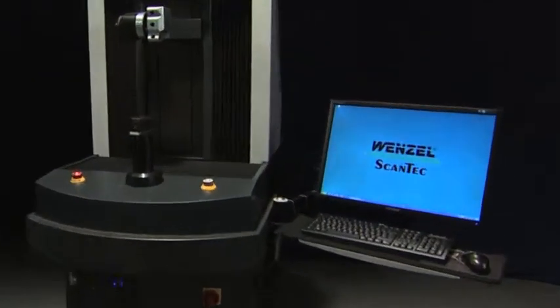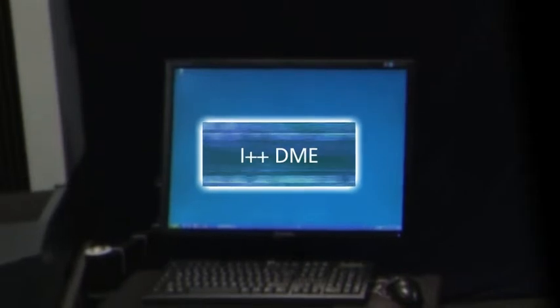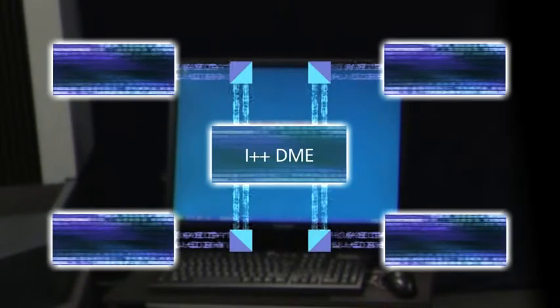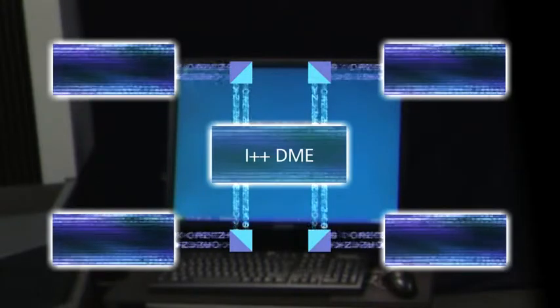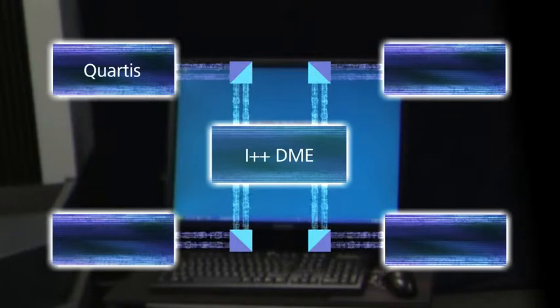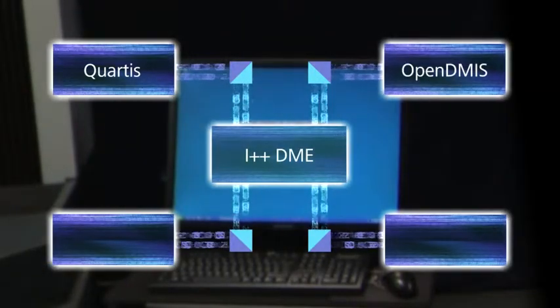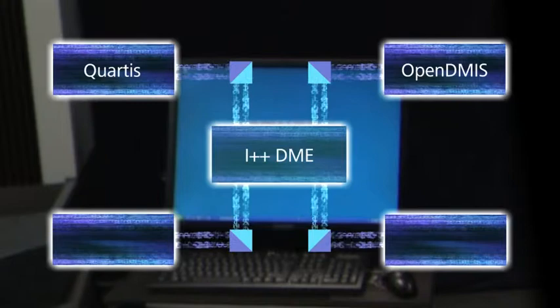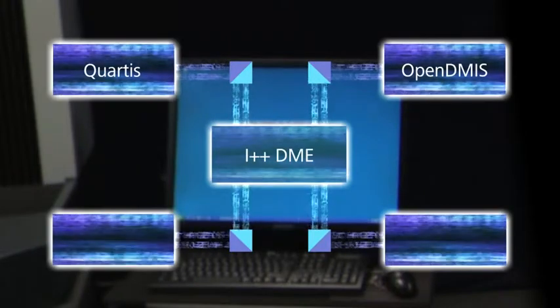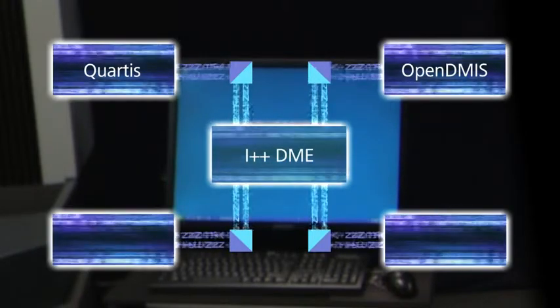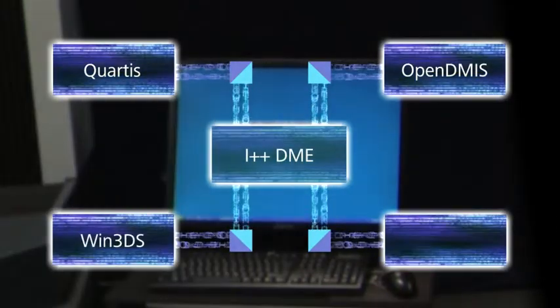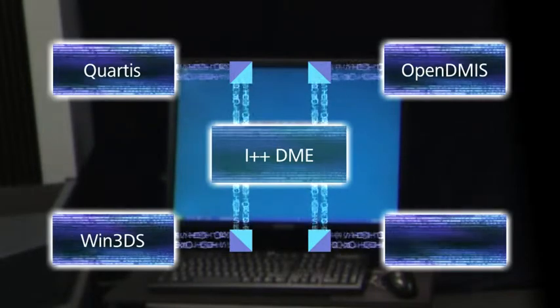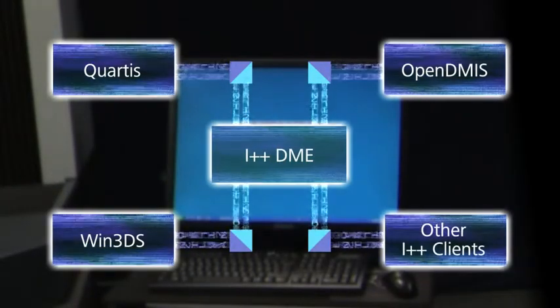Core utilizes the I++ DME interface allowing the unit to be supplied with a choice of softwares. Standard offerings include the benchmark Metrosoft Quartis from Metromec in Switzerland and the renowned OpenDMIS software. Both offer a shop floor program launch interface allowing machine usage by unskilled personnel. The comprehensive analysis software Win3DS from Wenzel Scantec can be supplied for the dedicated inspection of turbine blades.